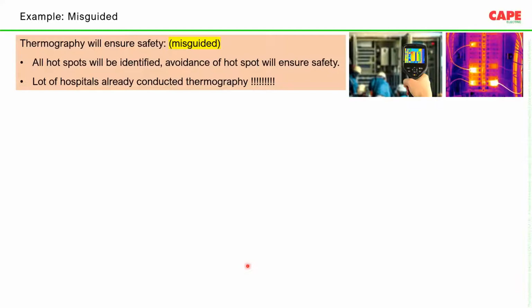As a result, hospitals go for thermography. A lot of people advocate it, and senior people also recommend that every hospital should have a thermography meter in order to ensure safety. Yes, of course, but you should understand that a thermography meter can only find a hot spot in a live, current carrying conductor.